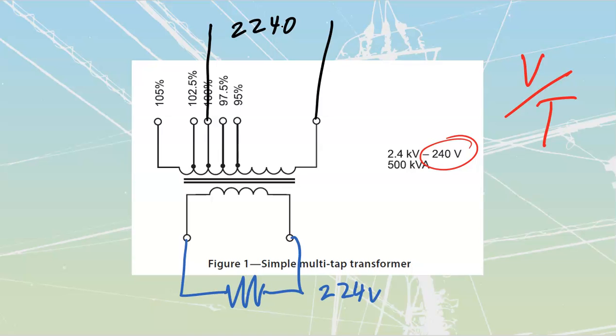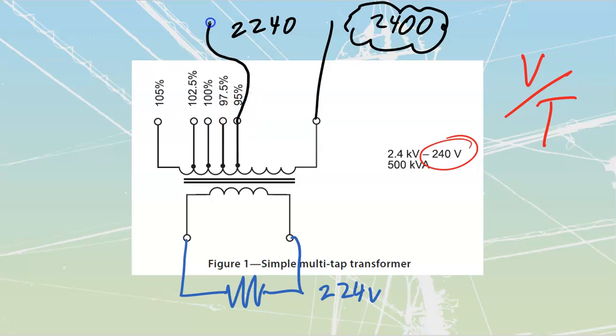That's now accounting for all the drops I have in the lines leading up to this: distribution, sub-distribution, power stingers coming down to the back end of the property where something's built, whatever it is. We've dropped from what we should have had of 2400. That's what my transformer's dream is, that it would be getting 2400, but instead we're feeding it 2240. So we just need to compensate for that. We're then going to take it over to this one based on that calculation: our actual divided by our rated. Our actual was 224.